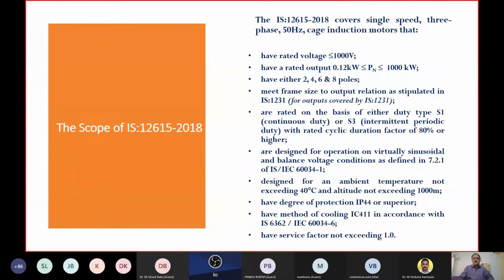Briefly, I will quickly read it so that it makes better sense to you. This standard covers single speed motors, so dual speed motors do not come under this standard. 3-phase only, single phase does not come. 50 hertz in India, 60 hertz does not come. Cage induction motors, any other motors are not covered here. Motor voltage will be rated for 1000 volts or less. We typically have 2 ratings, 415 and 690 under the LT. Rated outputs are from 0.12 kilowatt up to 1000 kilowatt, 2-pole, 4-pole, 6-pole, and 8 poles.